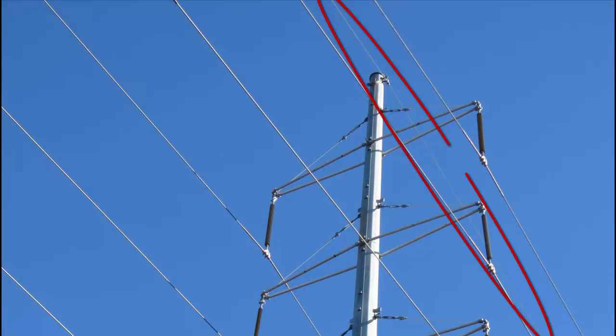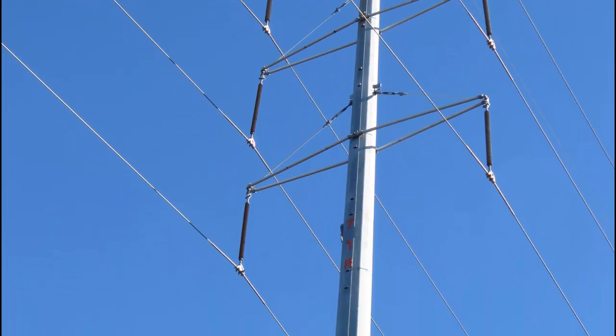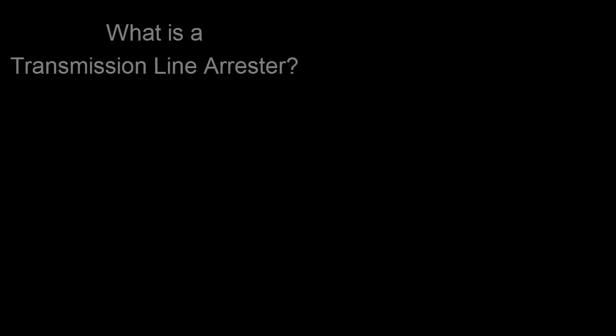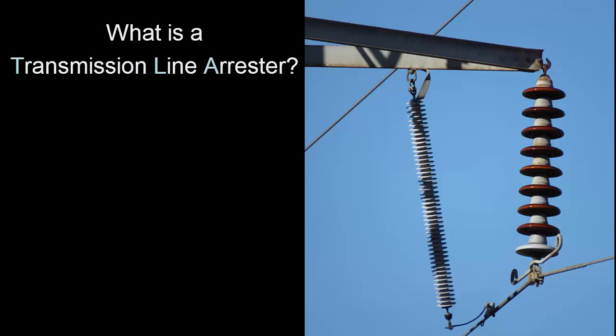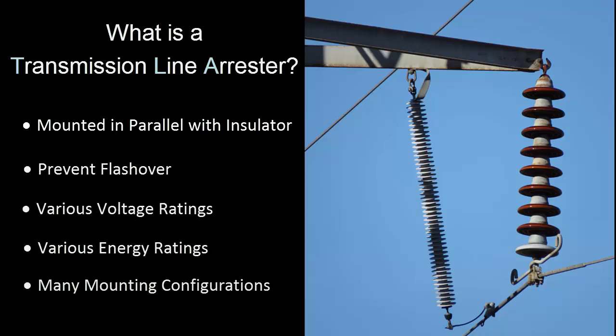Overhead shield wires had been the only cost-effective means of mitigating the effects of lightning until that moment. Since then, the TLA has shown its value not only in reducing lightning induced outages, but also in numerous ways which we will discuss here. A TLA is an arrestor mounted in parallel with a transmission insulator to prevent flashover of the insulator during various transient events. They come in various voltage ratings, energy ratings, and many mounting configurations.